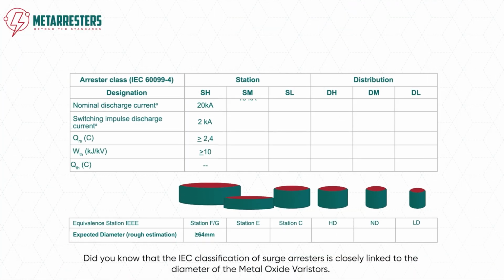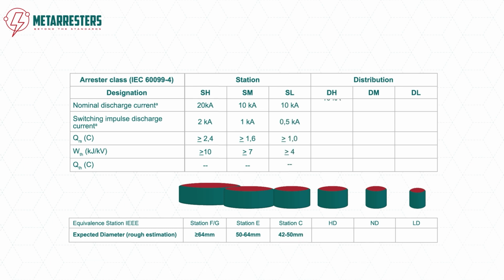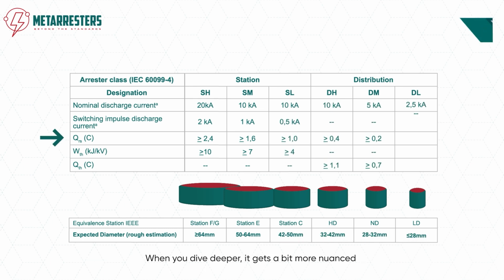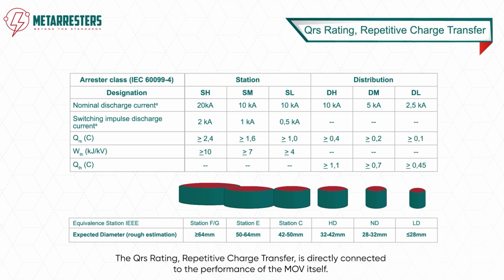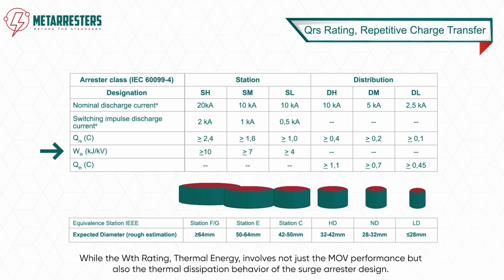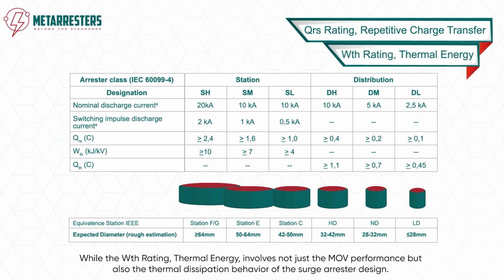Did you know that the IEC classification of surge arresters is closely linked to the diameter of the Metal Oxide Varistors? When you dive deeper, it gets a bit more nuanced. The QRS rating, repetitive charge transfer, is directly connected to the performance of the MOV itself, while the WTH rating, thermal energy, involves not just the MOV performance, but also the thermal dissipation behavior of the surge arrester design.